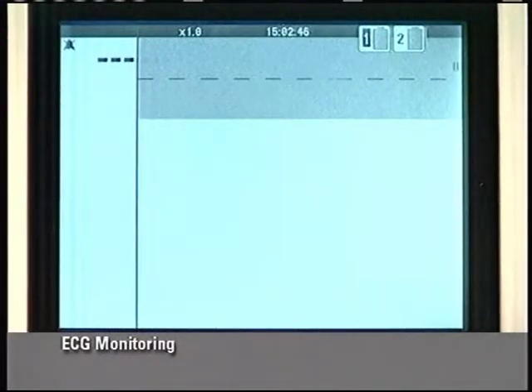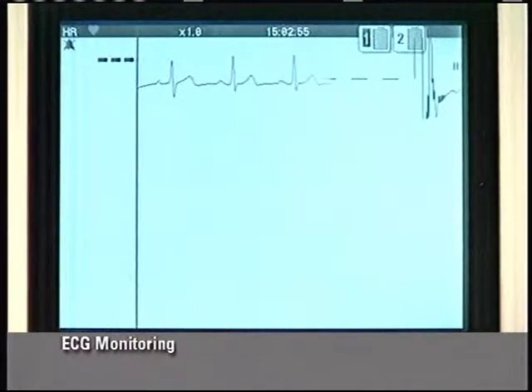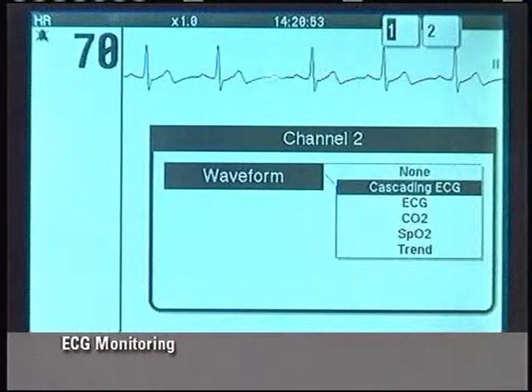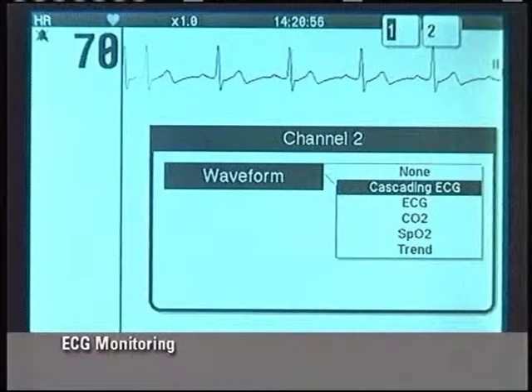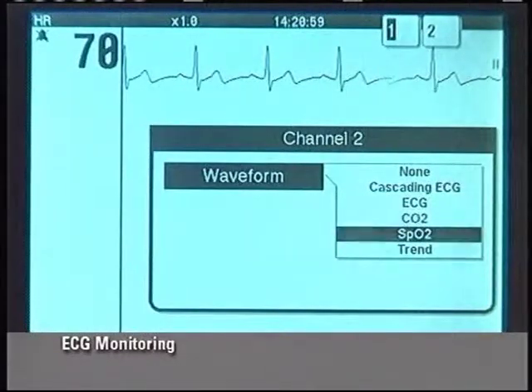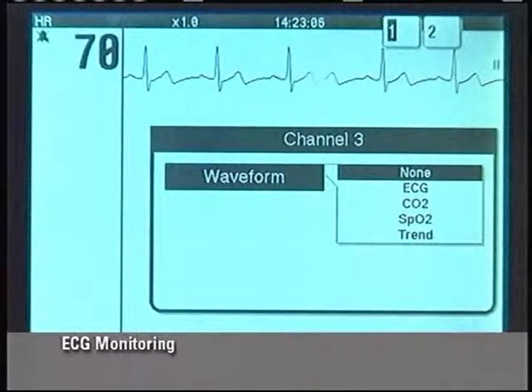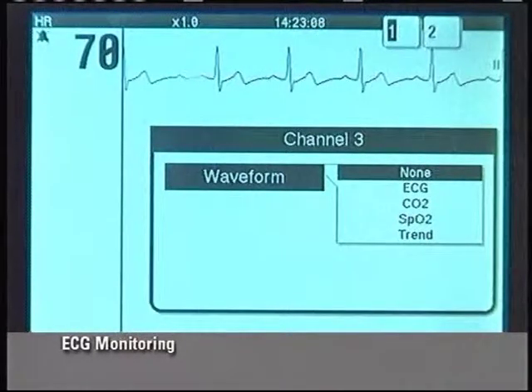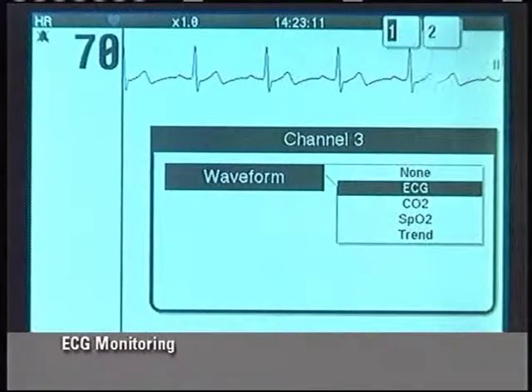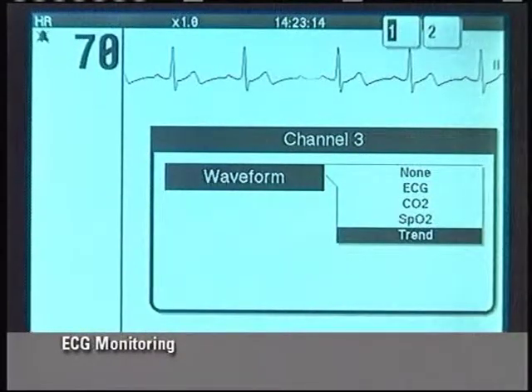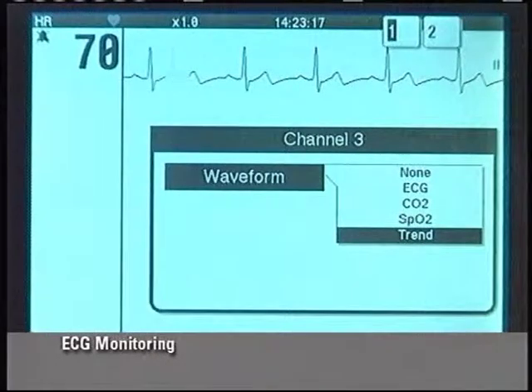The LifePak 12 defibrillator monitor screen can display up to 3 waveforms. The top waveform area is called Channel 1, the middle area is Channel 2, and the lower area is Channel 3. The ECG always displays in the top channel when the defibrillator is on. Channel 2 may be left blank or display a continuation of the Channel 1 ECG or one of the other monitoring parameters or a trend graph. Channel 3 is available only if a 100mm printer is installed. It may be left blank or display a different waveform or a trend graph. Consult the operating instructions for more information about using channels 2 and 3.